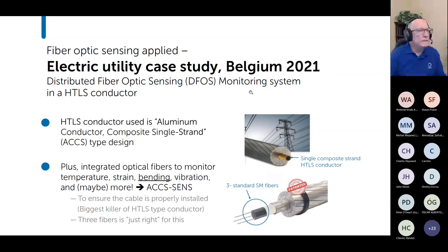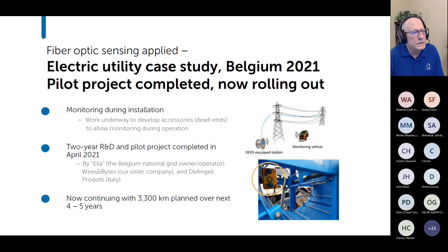So the particular type that we did on this project in Belgium, where the pilot project phase finished up earlier this year, we used a fully annealed aluminum conductor with a composite single strand core as opposed to a multi-strand core, because that worked better for the fiber. We used three fibers because it turns out that to detect that bending, three fibers is just right. Two fibers doesn't give you enough, right? Because it's possible for the core to be bent in a direction that doesn't get picked up. Four fibers is too much. You just don't need that many. Three fibers, it's like Goldilocks and the porridge, just right. And what you see is that the sensing unit is attached to the cable reel. And so as the cable is being pulled in, you're able to monitor what's going on. So that's just during installation.